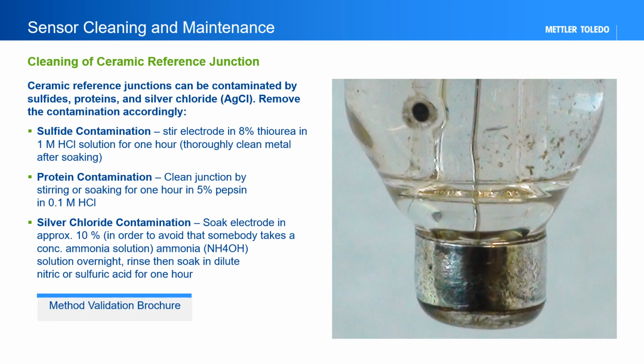A ceramic reference junction can be contaminated over time with sulfides, proteins, or silver chloride precipitate. This contamination can block the flow of the reference electrolyte and must be removed. Pictured here is a silver ring electrode with a ceramic reference junction contaminated with sulfide. Sulfide contamination can be removed by stirring or soaking for 1 hour in a solution of 8% thiourea and 1 molar hydrochloric acid. Protein contamination can be removed by stirring or soaking the electrode for 1 hour in a 5% pepsin and 0.1 molar hydrochloric acid solution. Silver chloride contamination can be removed with an overnight, approximately 8 hours or more, soaking in 10% ammonia. This must be followed with a thorough rinse and soak in a dilute acid.